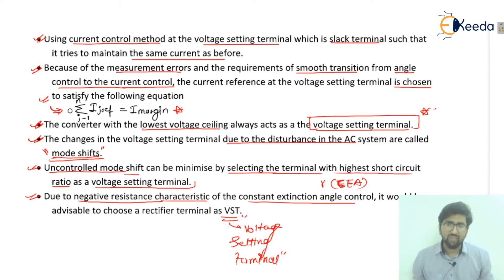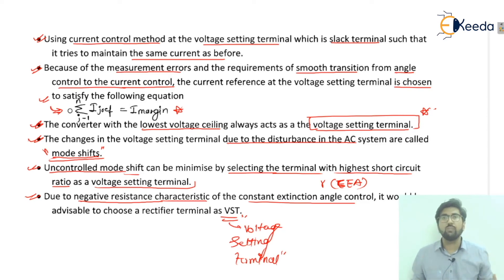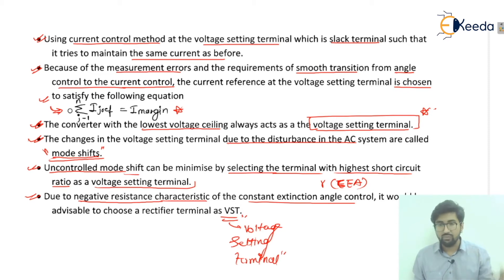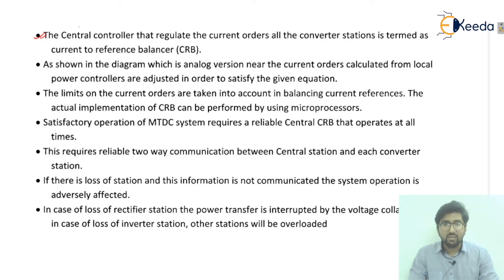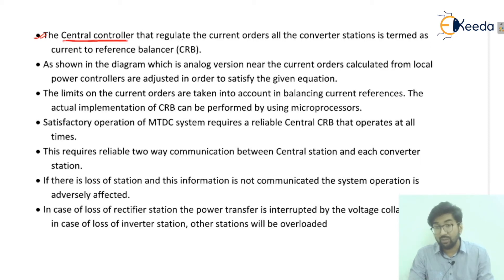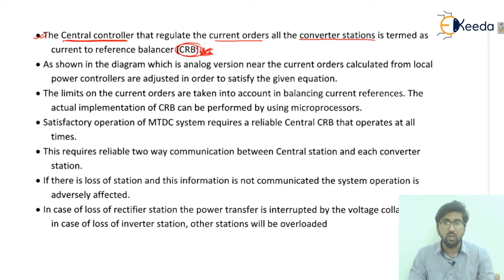Due to the negative resistance characteristics of the constant extinction angle (CEA) control on the inverter side — seen in the equivalent circuit as RC1 and minus RC2 — it would be advisable to use a rectifier terminal as the voltage-setting terminal (VST). The central controller that regulates current orders for all converter stations is termed the Current Reference Balancer (CRB).